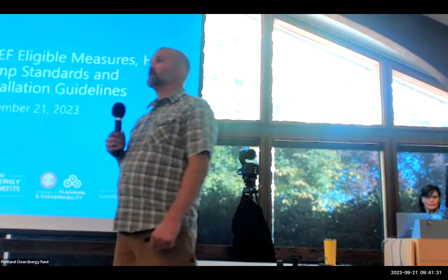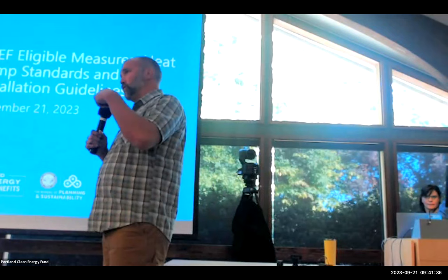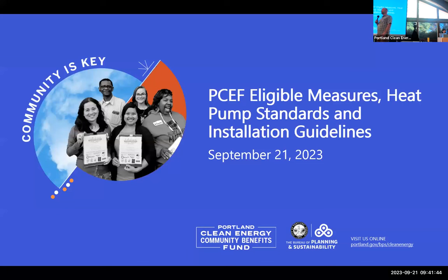There's one mistake on the ducted checklist, there's incorrect information about condensate. Please make a note on the copy that you gave me that is not the final copy. Yeah, the old line that says avoid condensate pumps. If it's a central fan coil indoor ducted unit, they're essential, right? For obviously removing condensate during the cooling dehumidification cycle of your indoor unit.